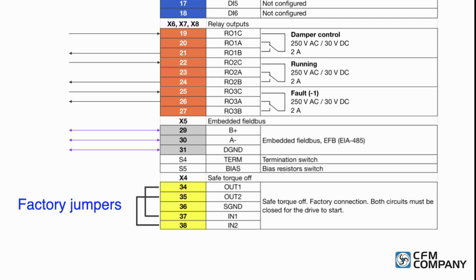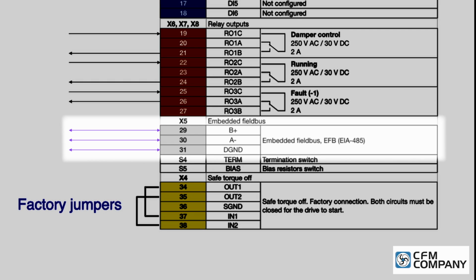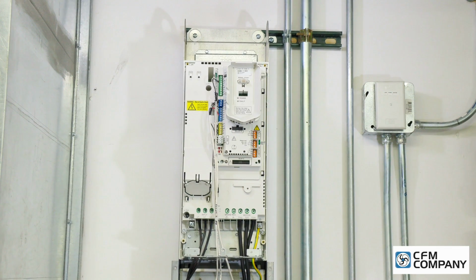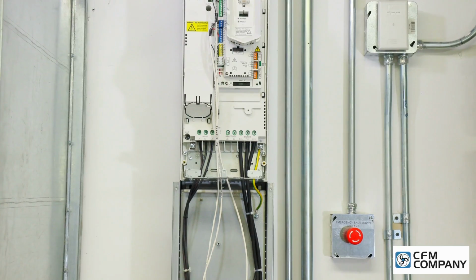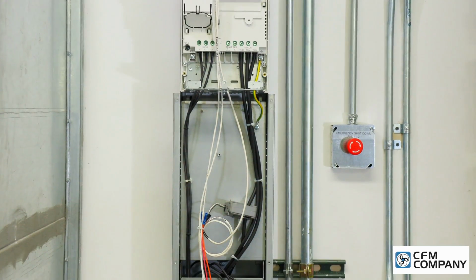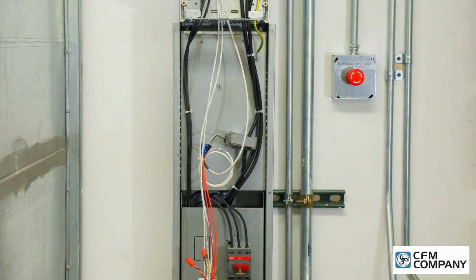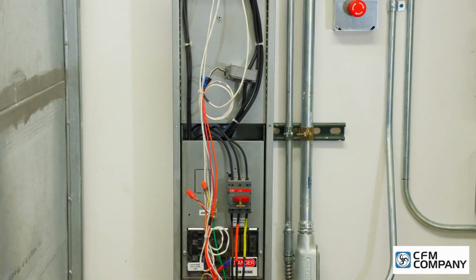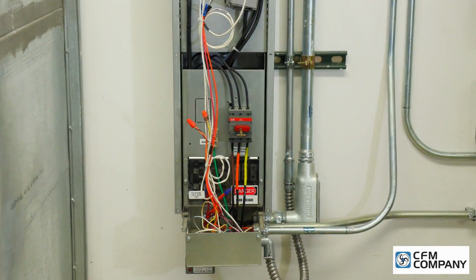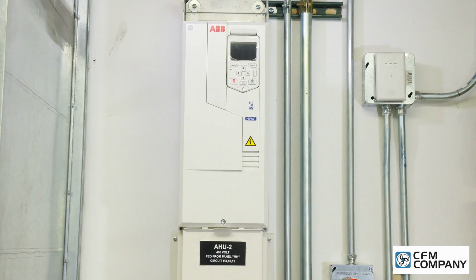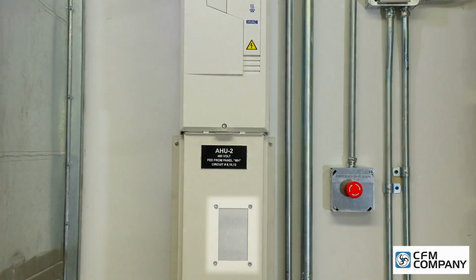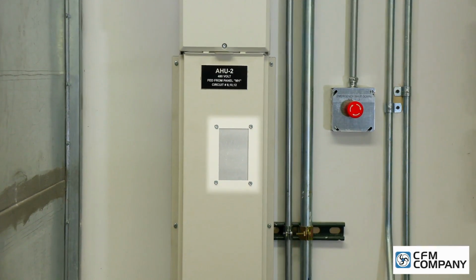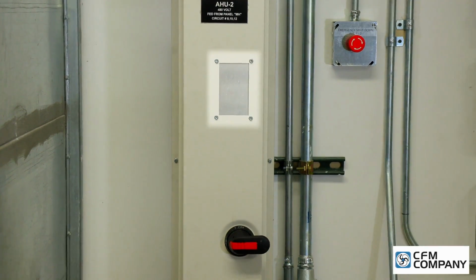If there are serial communications being used, land these wires on the embedded field bus terminals, EFB. With all the field wiring complete, use zip ties to contain the field wiring. Apply the drive cover and the bottom enclosure cover. Notice that the opening for the bypass control board has been covered to prevent access.